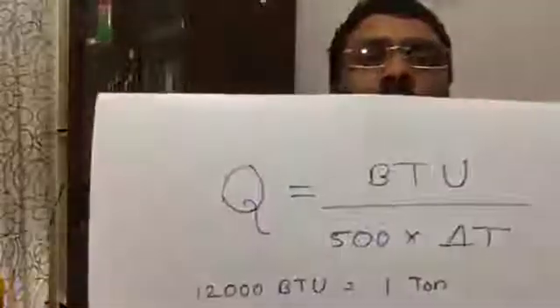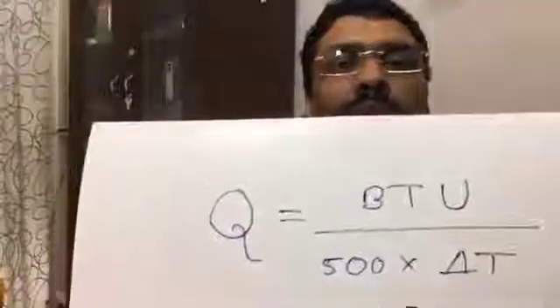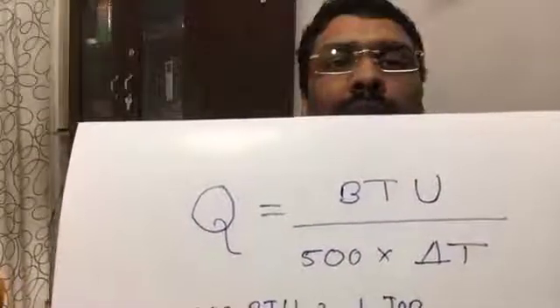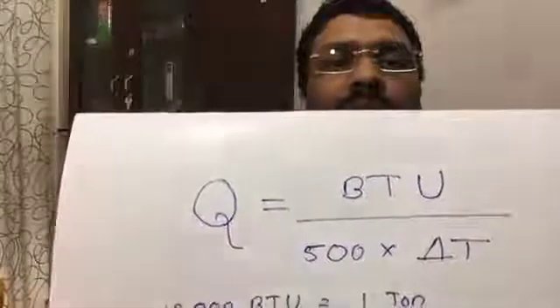This is what we are going to study about. For measuring the quantity of chilled water, there is a simple and easy equation: Q is equal to BTU divided by 500 into delta T. This is a very simple equation.